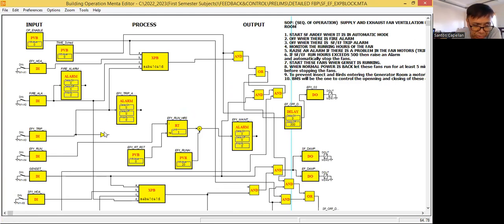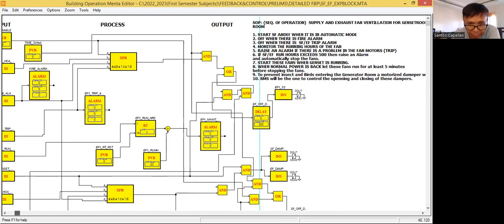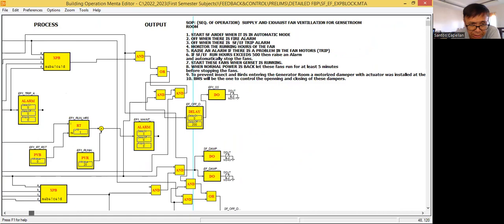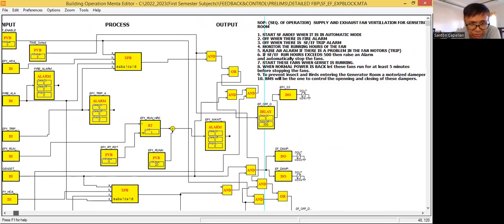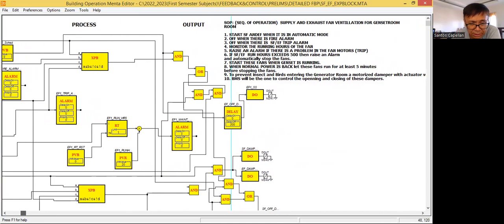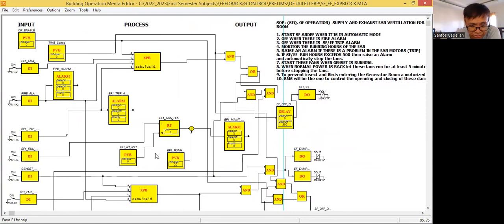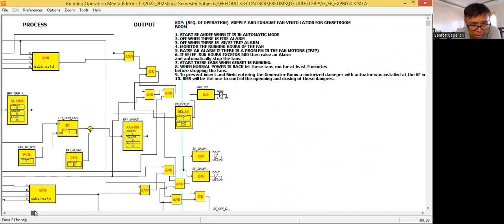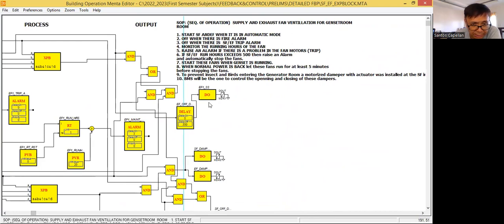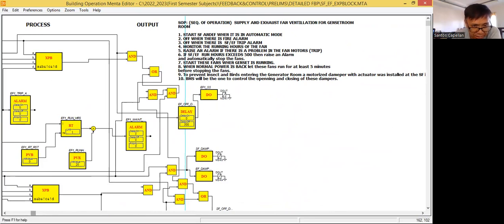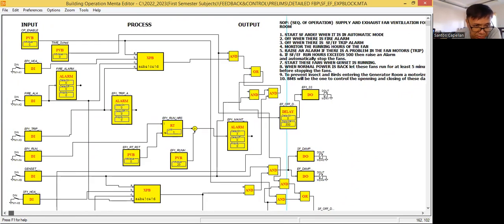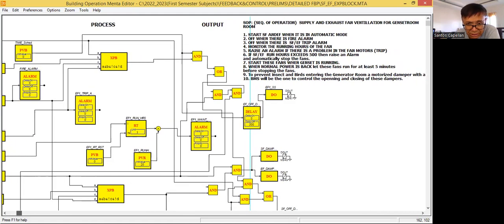I will try to remove this also. We have one AND gate here which is missing one input. This logic is tied to a time schedule. When the time schedule condition is also true, that is one reason to start the exhaust fan. But did we consider the genset here? We did not consider the genset.